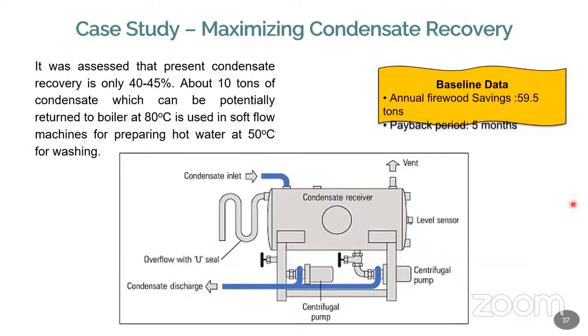Then maximize your condensate recovery. How much water you are feeding as input, and how much you recover, that is the very important part. In case you recover more than 50%, or more than 75%, more than 80%, it is very good.